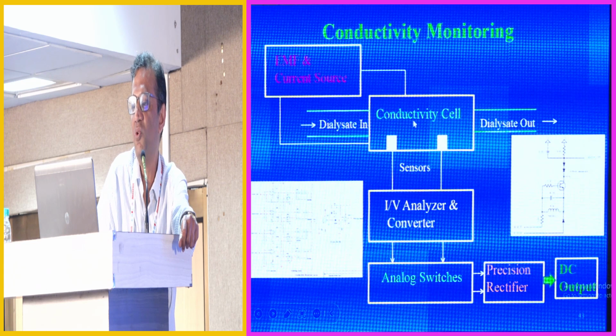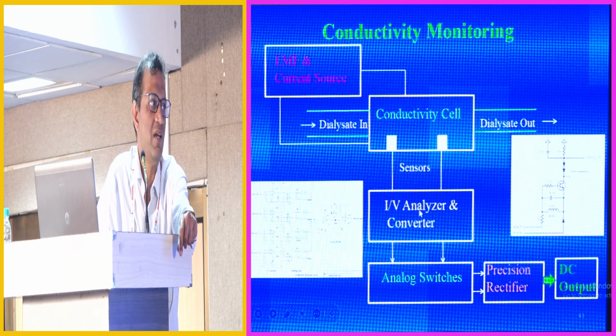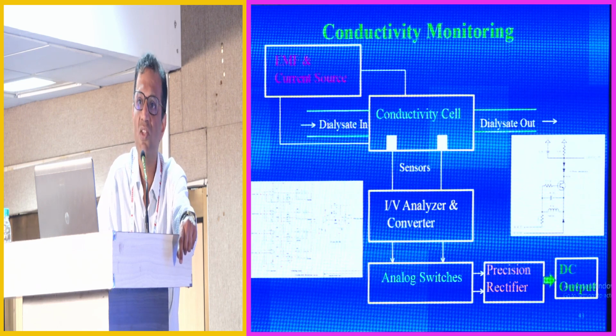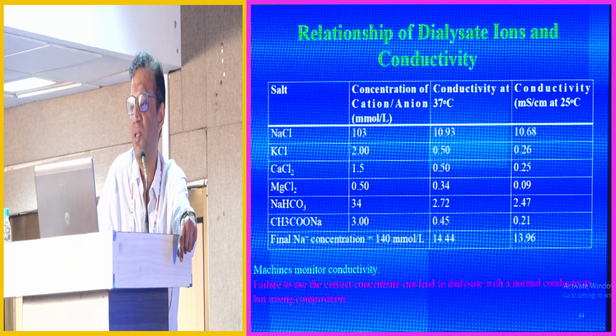The dialysate flows in and out of the conductivity cell, and a small current is passed across it during that time. Two sensors will measure the voltage that develops in the conductivity cell, and then an analyzer will measure the ratio of current to voltage, which is the conductance, convert it into a conductivity, feed it to the microprocessor unit, convert it into a digital signal, which is then displayed by the machine.